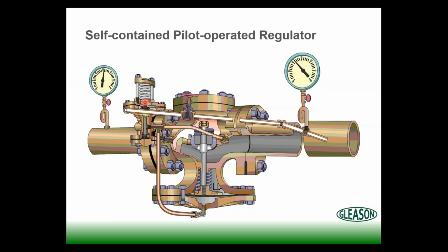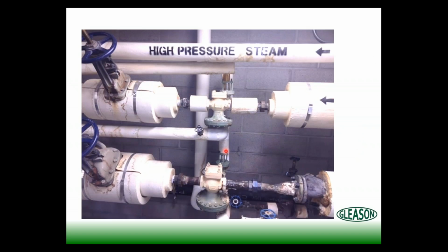This next slide is from a university we were in just recently. You can see here are the main valves for the regulators. The pilot's just behind them. You see they're coming up off the pilot and then sloping down. Well, what you don't see in the photograph, over here on the backside on the pipe tee, the springs are different colors for different pressure ranges that we're regulating to for these valves. And there's a whole different pile of different colored springs laying over here where the folks at this particular facility have been changing that spring because they can't get the accurate regulation they need. It has nothing to do with the spring. They've got the right spring in there right now, but the problem is they're not sloping down and away from the pilot. So that's a big deal there.